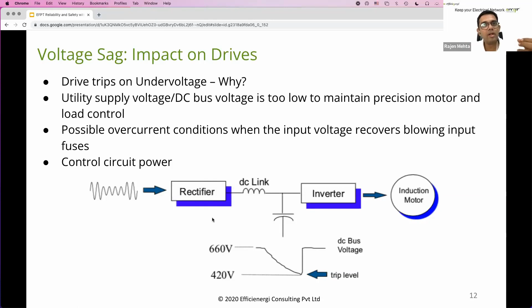So what are the measures by which you can reduce the impact of these voltage sags? Our focus is always on no-cost or low-cost measures to protect your equipment first and foremost. Some of these are listed on your screen. Most commonly, connect large loads directly to the PCC. Do not have a large compressor motor connected two or three levels downstream, all the way down from an MCC.